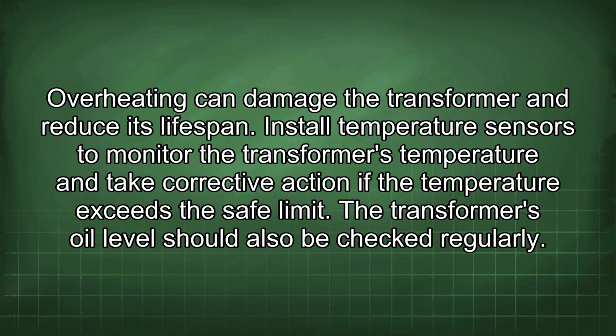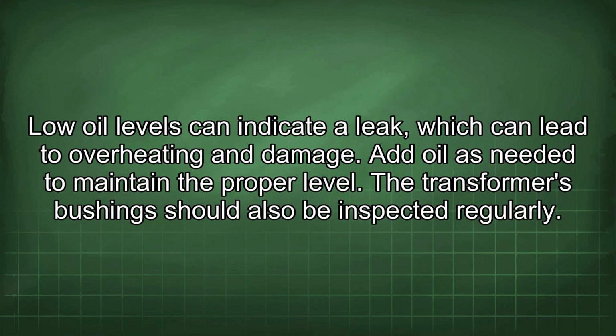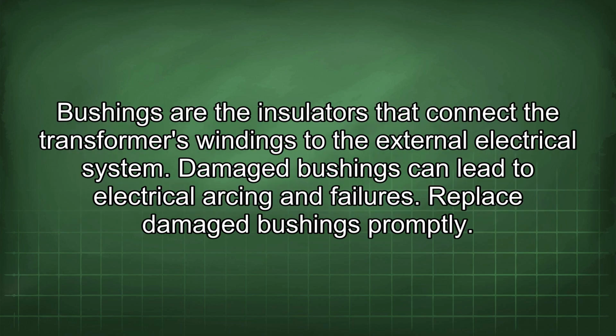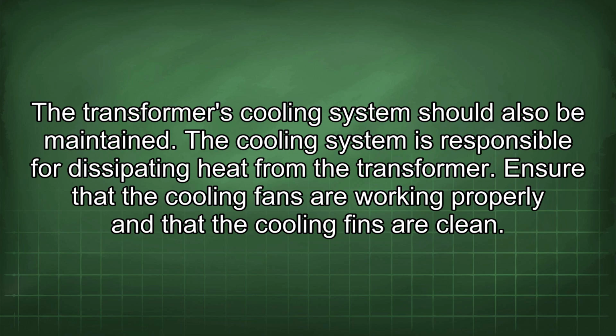The transformer's oil level should also be checked regularly. Low oil levels can indicate a leak, which can lead to overheating and damage. Add oil as needed to maintain the proper level. The transformer's bushings should also be inspected regularly. Bushings are the insulators that connect the transformer's windings to the external electrical system. Damaged bushings can lead to electrical arcing and failures. Replace damaged bushings promptly. The transformer's cooling system should also be maintained. The cooling system is responsible for dissipating heat from the transformer. Ensure that the cooling fans are working properly and that the cooling fins are clean.